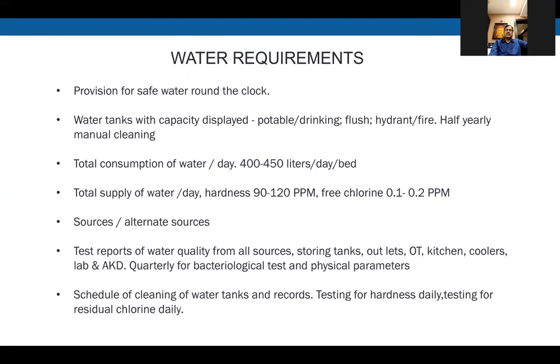Total consumption of water as per the norms is around 400 to 450 liters per day per bed. This is a general assumption, but it does not include water which is used in the gardens, or water used for various other requirements of cleaning, etc. But overall, a general requirement is around 450 liters per day per bed. And the total supply of water, we have to note down. We must understand how much is sufficient for the hospital or not. The hardness prescribed by IS 10500 is around 90 to 120 ppm, and the free chlorine which should be tested on a daily basis is 0.1 to 0.2 ppm ideally.